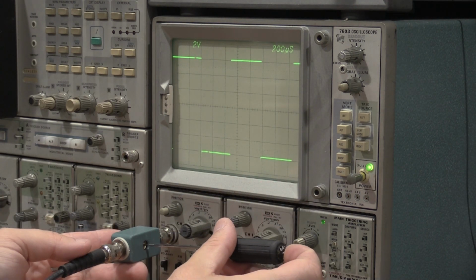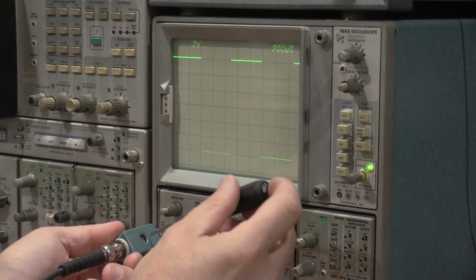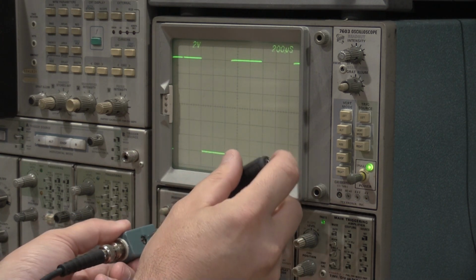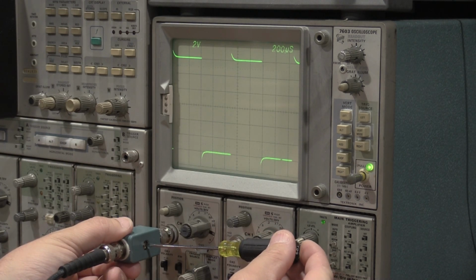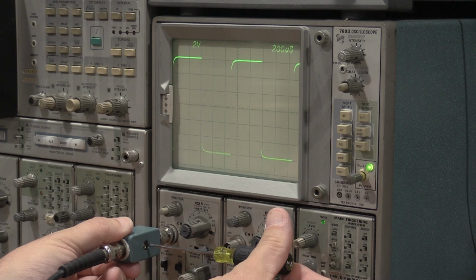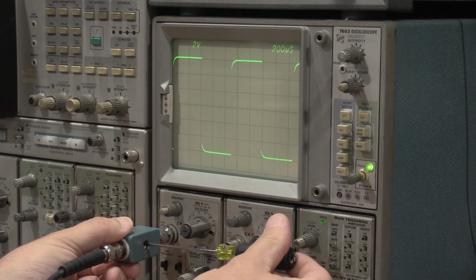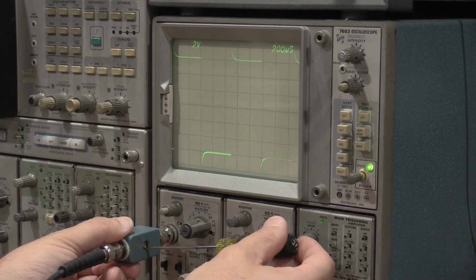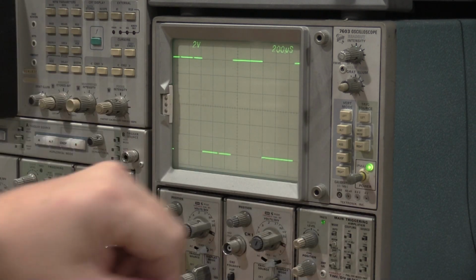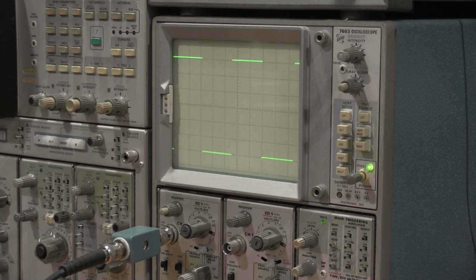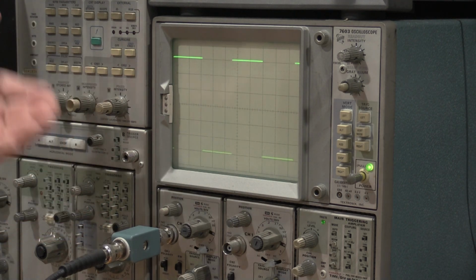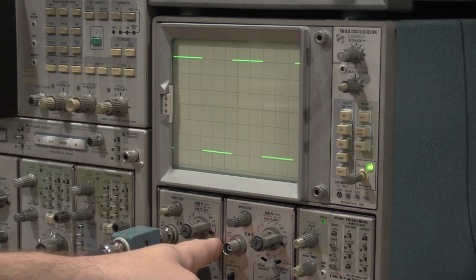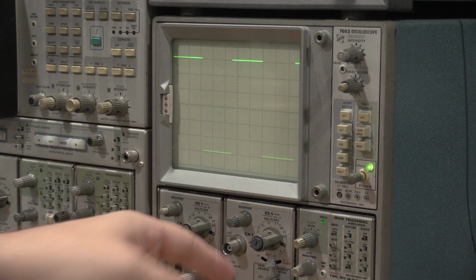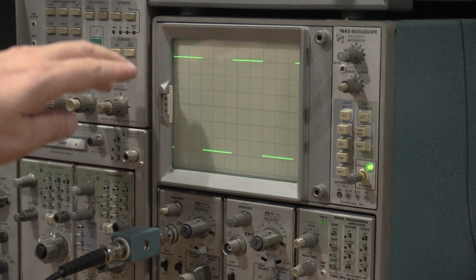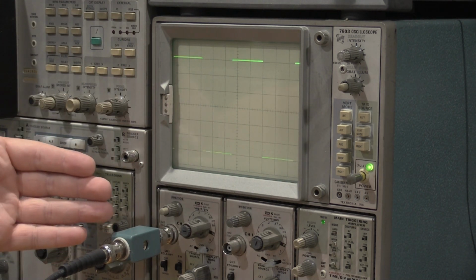If I adjust the tuning capacitor down in the bottom, well, don't short it out, but adjust it, we can see the compensation goes up, and then we can overdamp it. So this is underdamped, overcompensated, undercompensated, and then we can make it just right. So now that would be set up for doing the alignment. So it looks good. If we were setting this up to do an alignment, it would be on the 10 millivolt range. But this is now ready to align the rest of the attenuator section.